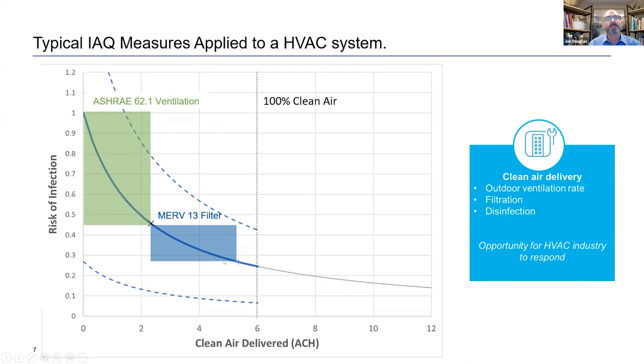On this chart, you can see that the curve stops at 6. The reason I did that is that this system only delivers 6 air changes per hour. So the best we can actually do with a centralized HVAC system would be 100% clean air, which would be 6 air changes per hour. If we want to reduce the risk further by going down this line, we need to add a source of clean air. An important thing to get here is that the amount of risk reduction delivered by the HVAC system is a function of the airflow delivered by the HVAC system.